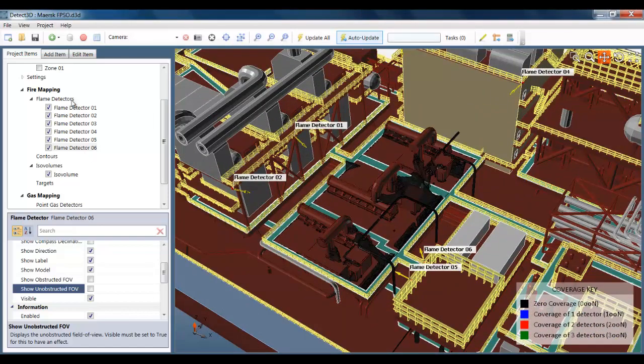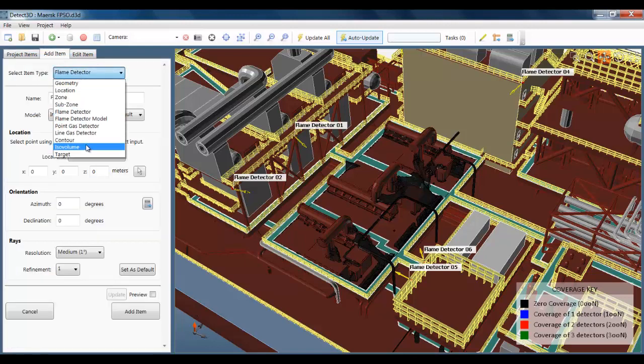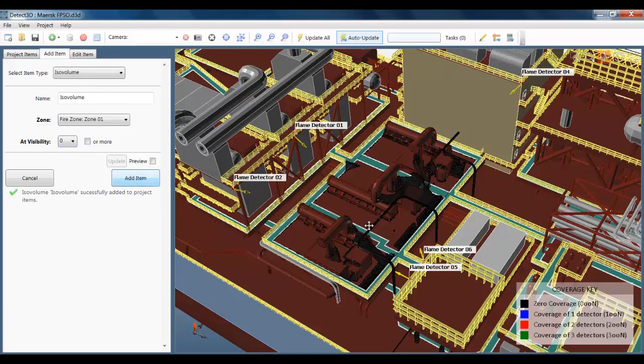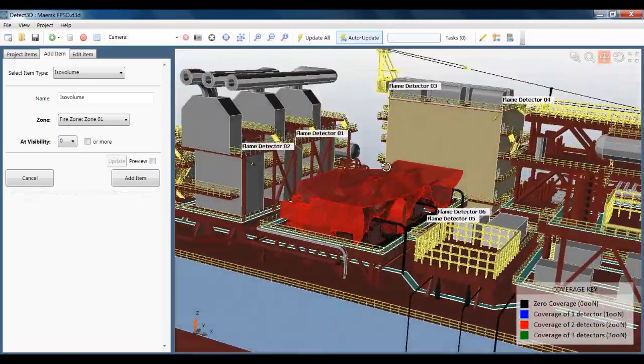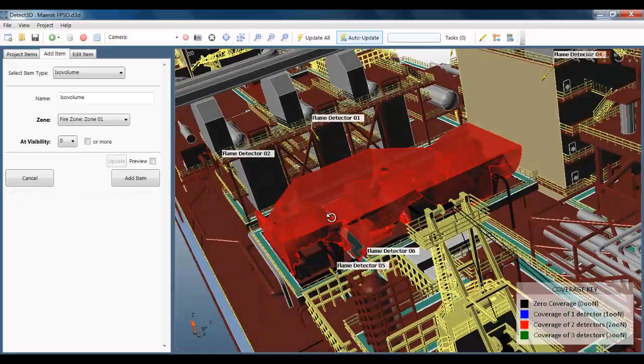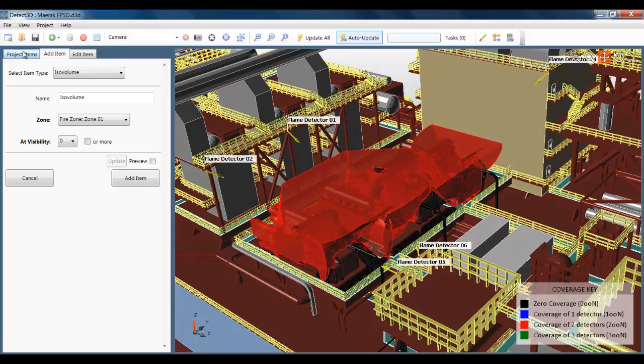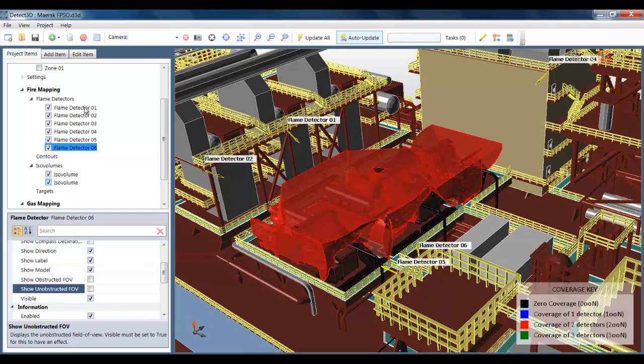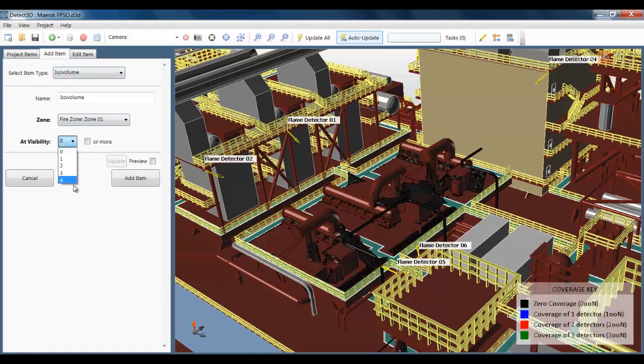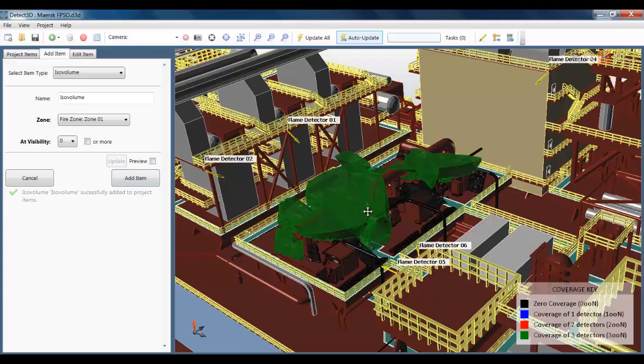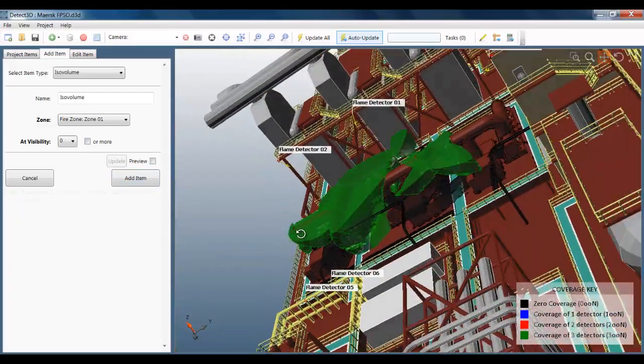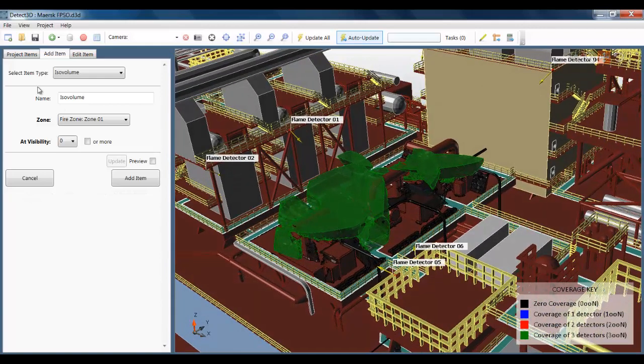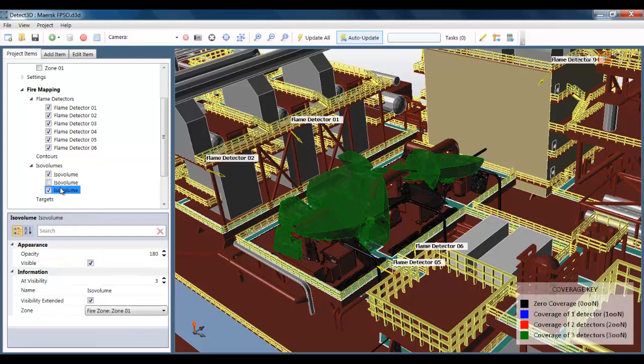Now I've just added an ISO volume at zero visibility, but I can see all the results using ISO volumes. Here I'm just adding one at two or more, which is going to appear in red. So this is all the volume of the fire zone that's visible to two or more flame detectors. I'm just going to turn that one off. And I'm going to add another one at three or more. This is useful if three or more is too much. So you can see areas which are over-covered. And it helps you position detectors to point them more towards blind spots and out of areas that have three or more flame detectors.